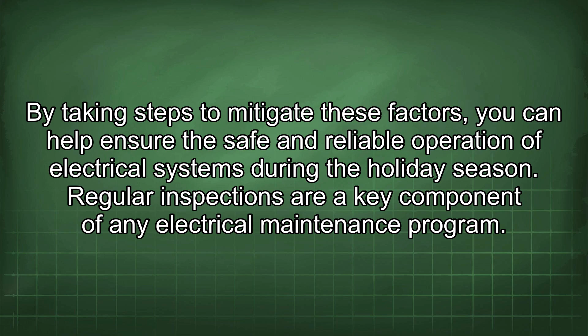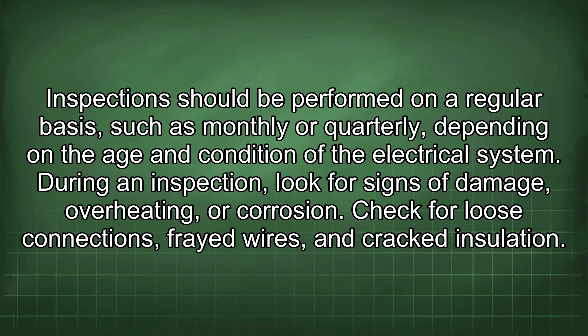Inspections should be performed on a regular basis, such as monthly or quarterly, depending on the age and condition of the electrical system. During an inspection, look for signs of damage, overheating, or corrosion. Check for loose connections, frayed wires, and cracked insulation. Test circuit breakers to ensure that they are functioning properly. Clean equipment to remove dust and debris.